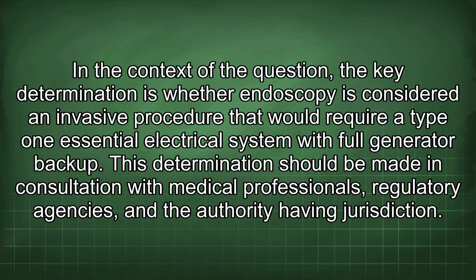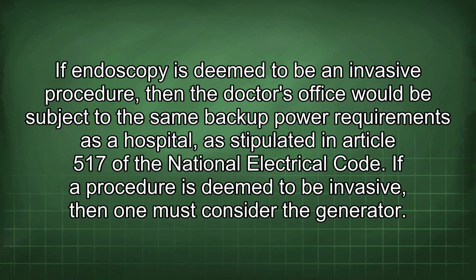This determination should be made in consultation with medical professionals, regulatory agencies, and the authority having jurisdiction. If endoscopy is deemed to be an invasive procedure, then the doctor's office would be subject to the same backup power requirements as a hospital, as stipulated in Article 517 of the National Electrical Code. If a procedure is deemed to be invasive, then one must consider the generator.